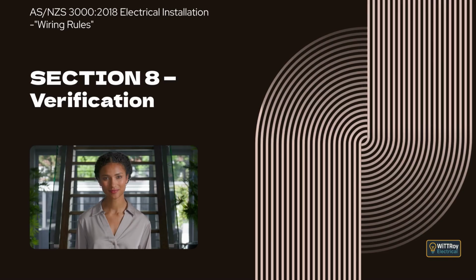Clause 8.3.6.2 Method. This clause explains that insulation integrity is tested by applying a direct current test voltage, typically 500 volts for low-voltage circuits. It also explains exceptions where equipment may need to be disconnected or switched off before testing to avoid damage, or where a reduced test voltage may be used for particular circuits.